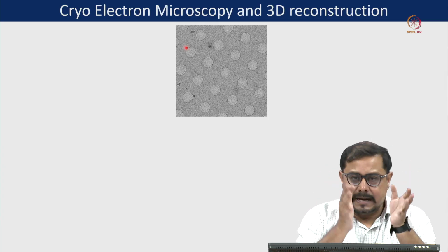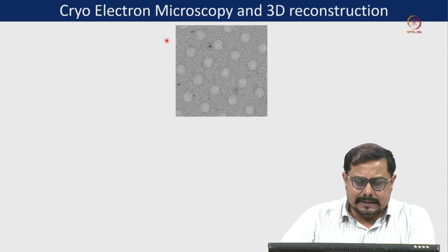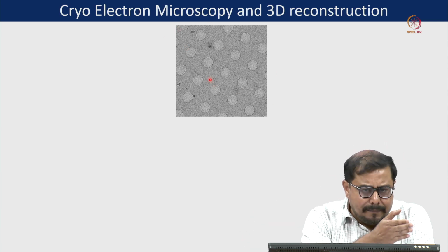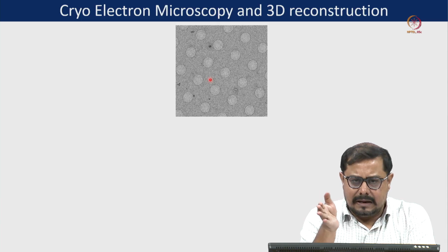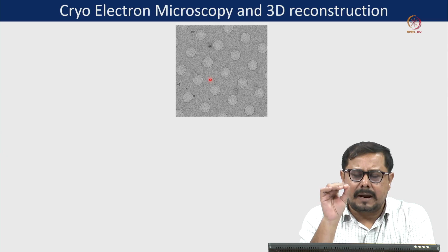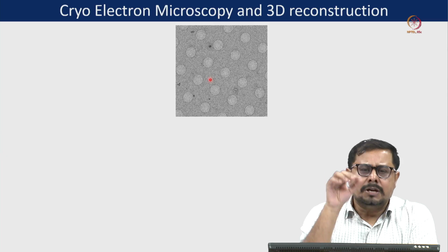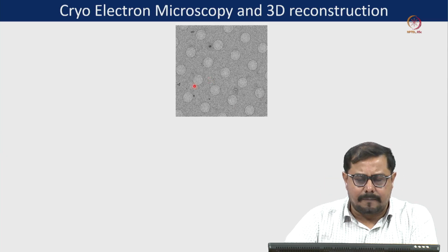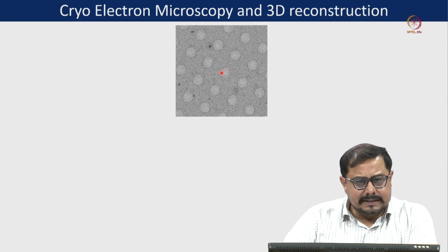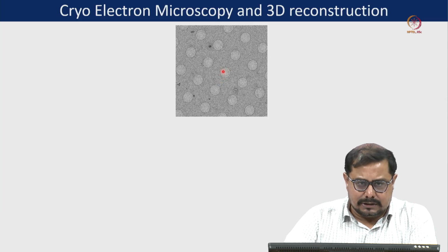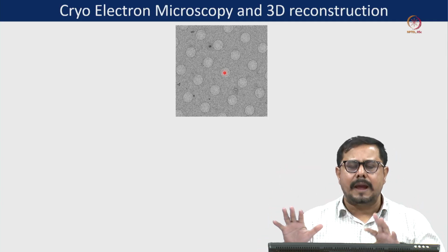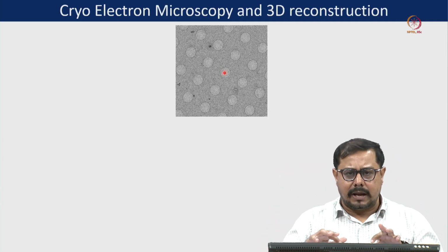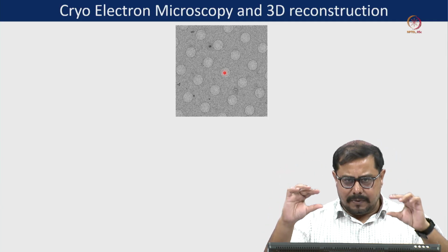When you are screening those grids, you can see this is one of the grid squares we are looking at. I will come back to that particular part when you image a grid at different magnifications and see what appears. Here, just consider this is one of my grids, and as I already told, the sample is inside this particular hole and it is in a fixed condition, it cannot move anymore. The sample cannot rotate, so this is completely fixed.